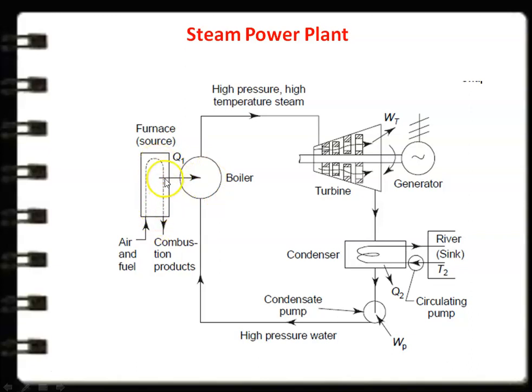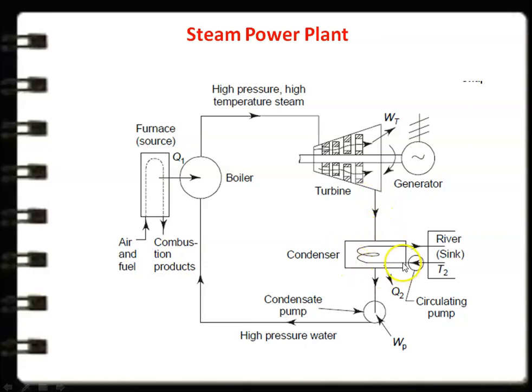Heat is given to the boiler from the furnace, where burning of the fuel takes place — this may be a liquid fuel or solid fuel. The hot gases are produced, and the heat is given to the boiler, which converts water into steam. The high-pressure, high-temperature steam from the boiler enters the steam turbine. In the steam turbine, we have multiple stages. The steam is expanded in the turbine, work is produced (Wt), and the steam leaves at low quality. The wet steam leaving the turbine goes to the condenser, where it is condensed using water from a river or lake, and the heat is rejected.